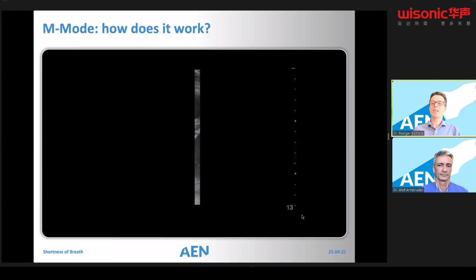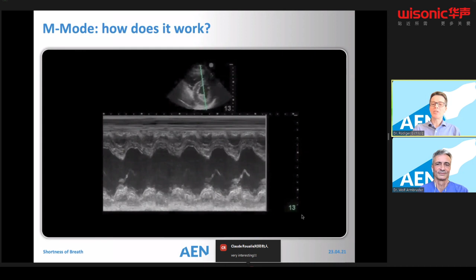And all the signals from this particular vertical line give the ECG-like pattern. We get all the motions that are on this particular vertical line. So every white dot that moves will get curvy, and every black dot, for instance, that's not going to move will result in a black line. And now we used to understand M-mode as a very specialized working mode of the machine that only cardiologists use, but no, it's different now. We also can use it.